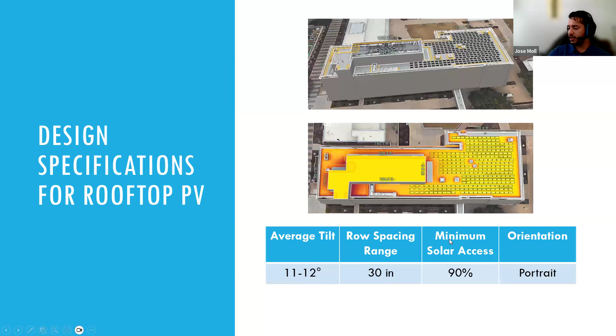Here we have the specifics for this building, where each rooftop system is wired in the following manner. We used Silfab 500-watt solar PV modules equipped with rapid shutdown, along with SMA Tripower Core 1 inverters, interconnected with the assistance of an ATS, and then connected to the main distribution panel for the building.